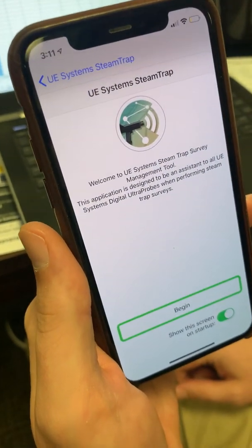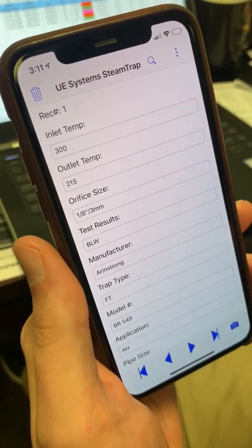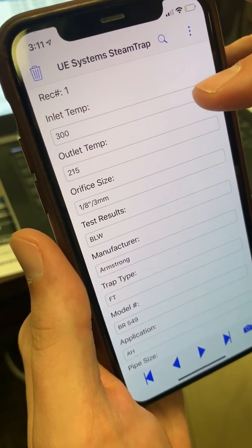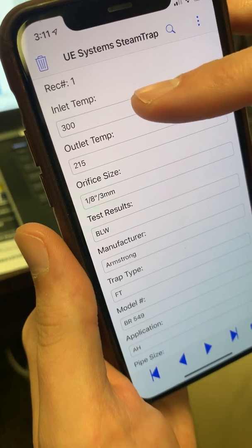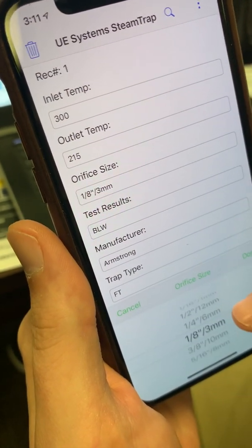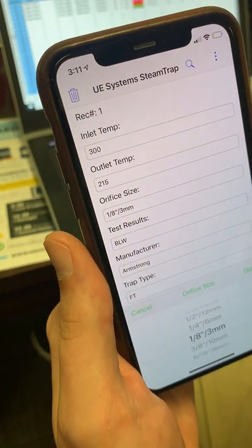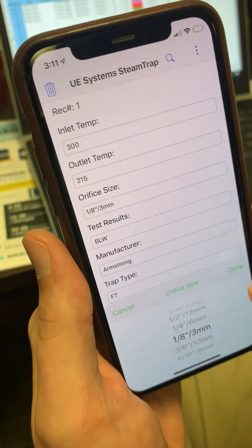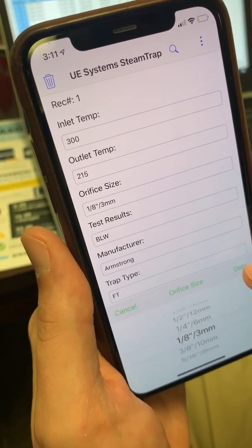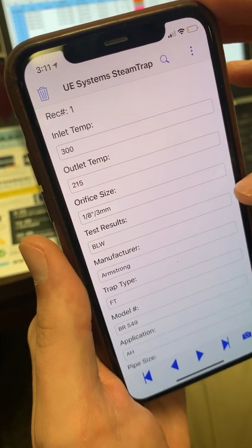Just tap the UE System Steam Trap app and hit Begin. I've already got some numbers plugged in so we can quickly move through it. Type in your inlet and outlet temps, then your orifice size — there are a couple of different size options. If you don't know what size to use, typically people go with one-eighth of an inch, as it yields a conservative estimate and is one of the more common orifice sizes.